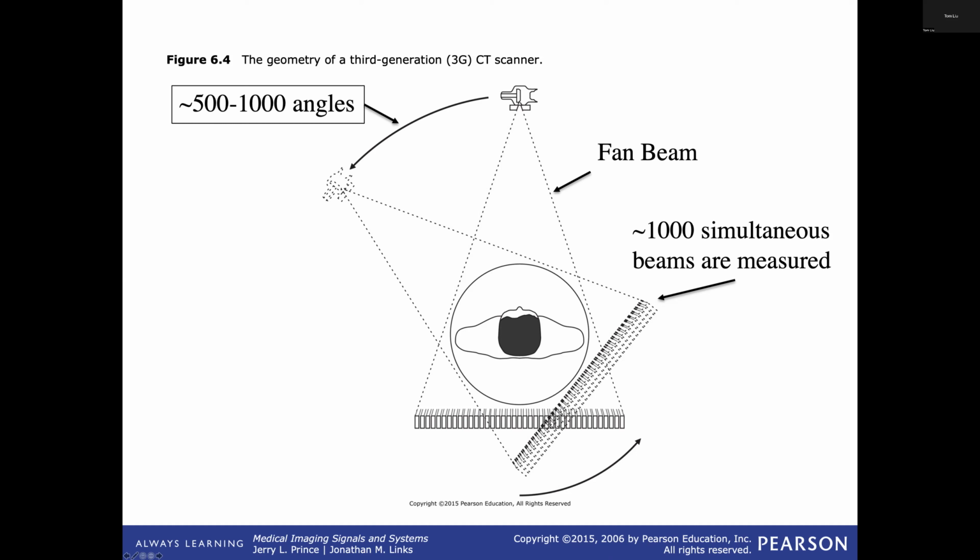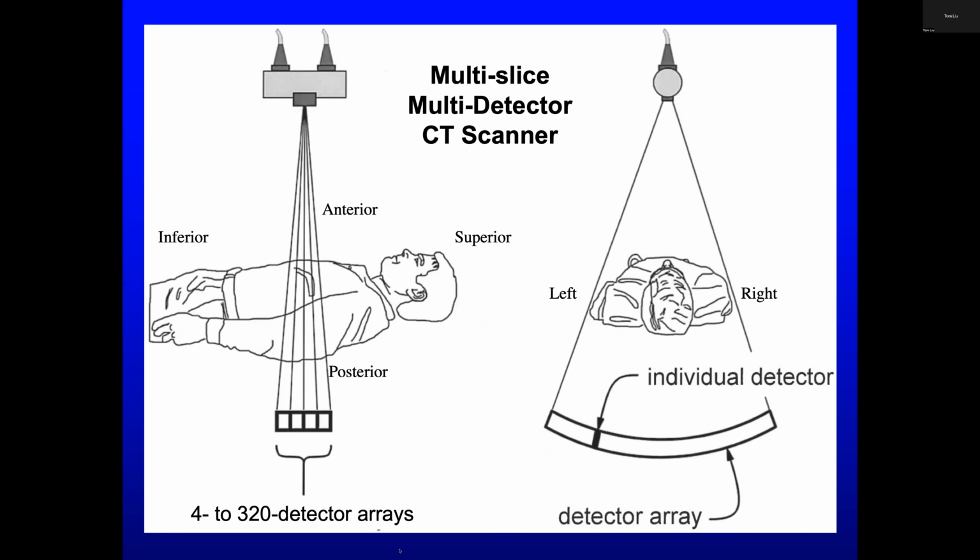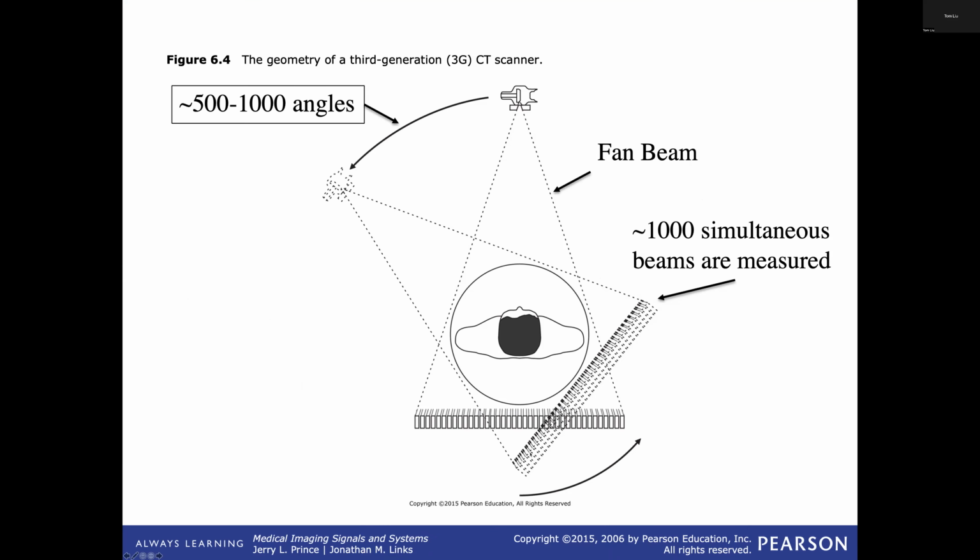And for many years, this is the way CT was done commercially, right? Before I go on, there were very many connections to these detectors, and that data had to go out onto a computer on usually some kind of ribbon cable that came off the scanner. And in order to get that data out, they would rotate the scanner and the ribbon cable would rotate with the gantry, right? And then you'd have to stop and rotate back the other way because if you kept going, the ribbon cable would just come off, right?